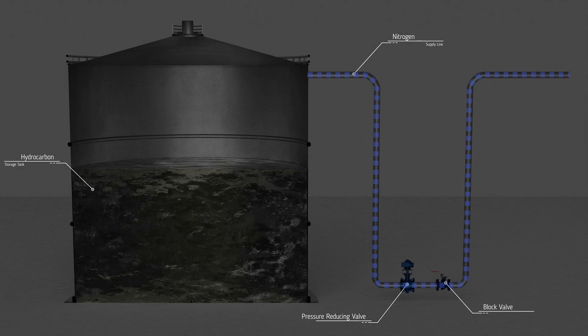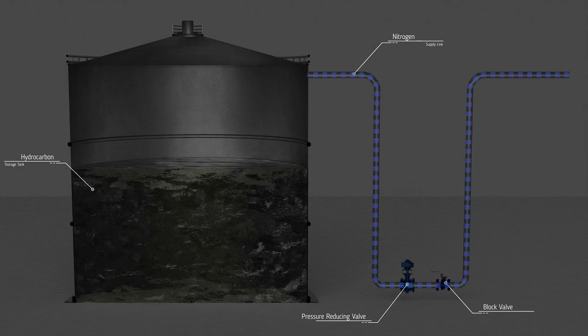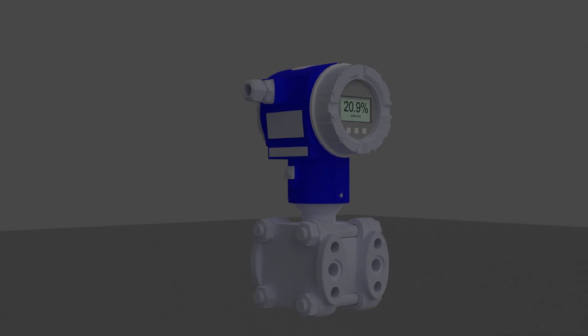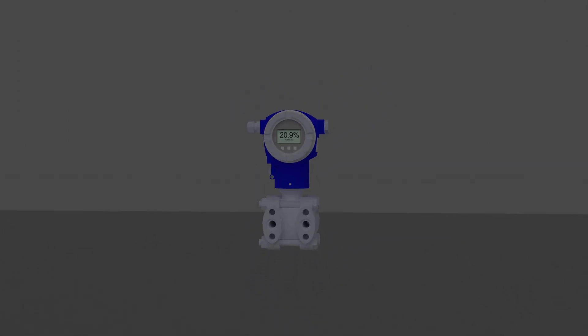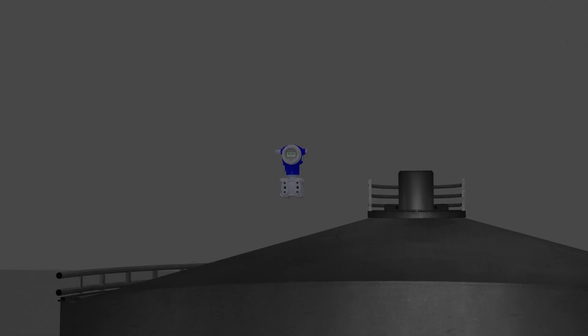It is not sufficient to check that the nitrogen is open to the tank. The atmosphere in the tank should be tested with an oxygen analyzer to make sure that the oxygen concentration is below 5% or other specific LEL.